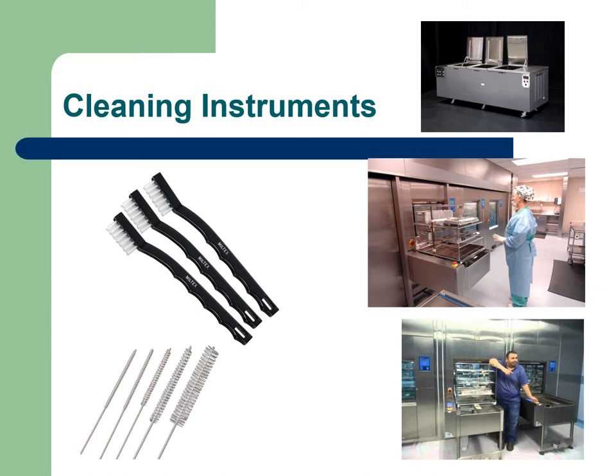I chose these two pictures - the one in the middle right is on the decon side, the dirty side. That cart gets loaded with instrument trays and gets pushed into the washer. When the washer is done washing, another side opens up on the prep and pack side. So we pull them out on the clean side and push them in on the dirty side. They get washed, somebody hears the washer alarming on the clean side, they hit the button, and pull it out on the clean side - that's how that works.